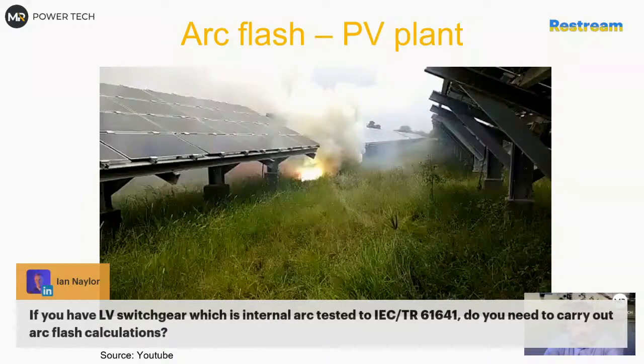So IEC 61641 for arc rated, let's say arc resistant, switchgear is a very nice thing to have, but it is for low voltage switchgear. The problem with it is that if you work on low voltage, it's very easy to open everything. And for example, you do some infrared scanning, you do some testing, you do some measurements. And at this point, you don't have your rating anymore. And so typically, yes, you need to do arc flash calculations just to know what your arc flash incident energy is at this switchgear.